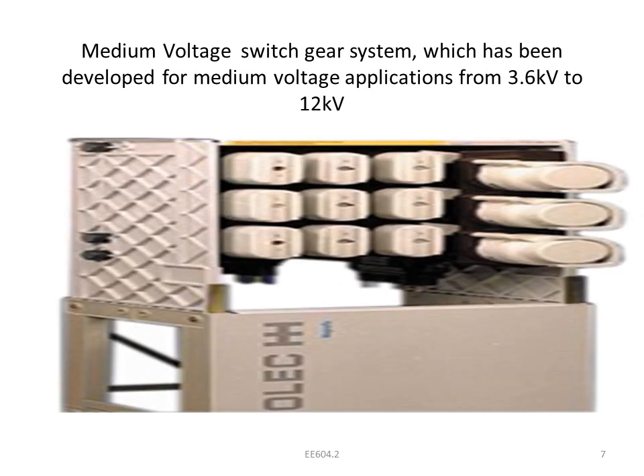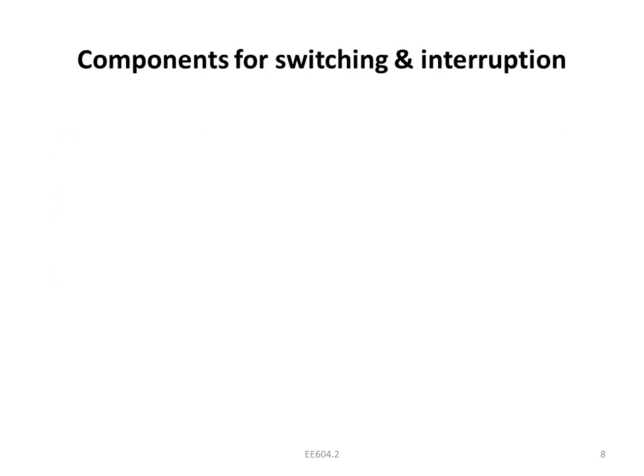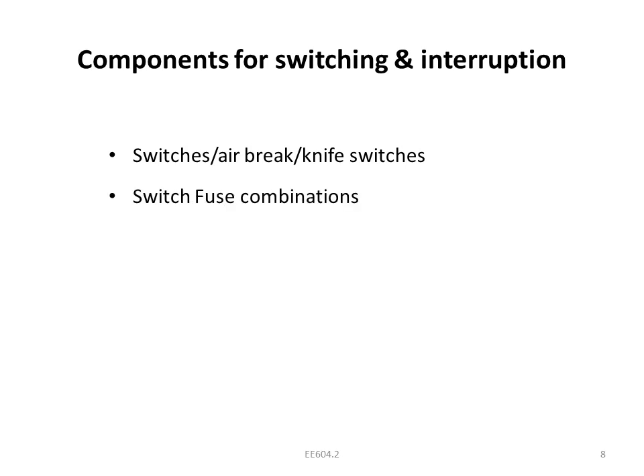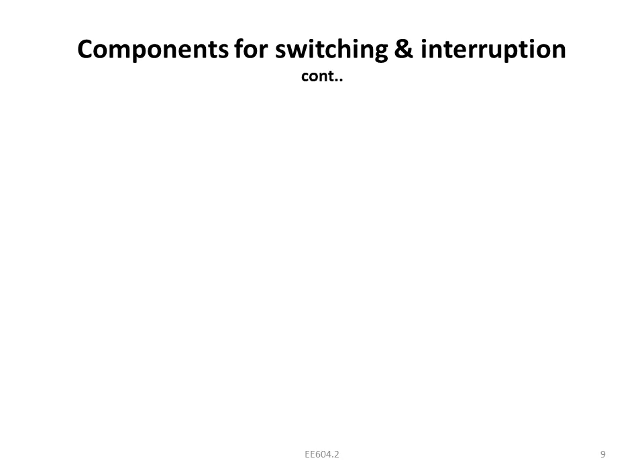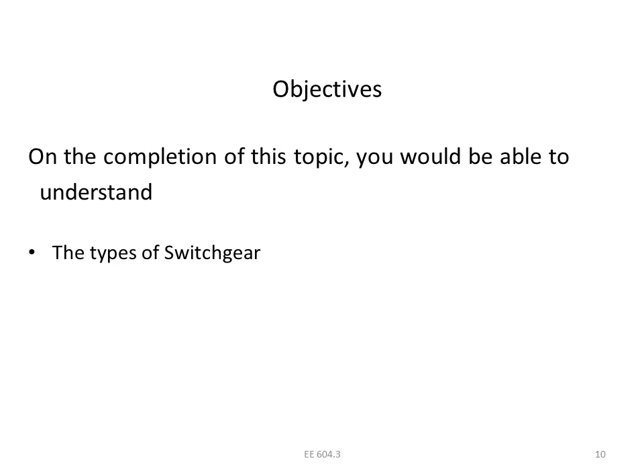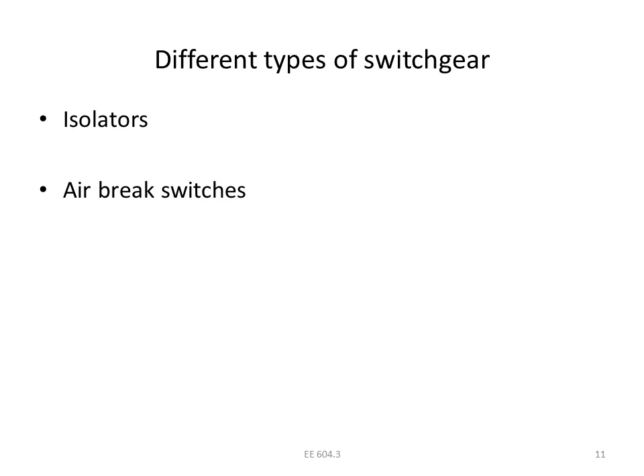This is one type of switchgear equipment you can see. Next, the components for switching and interruption: switches, air break switches, knife switches, switch-fuse combinations, circuit breakers and HRC fuses. Then relays, isolators, earthing switches, and instrument transformers, such as potential transformers. There are different types of switchgear: isolators, air break switches and knife switches are all different. Switches differ in their applications, and circuit breakers are used for large kV applications.